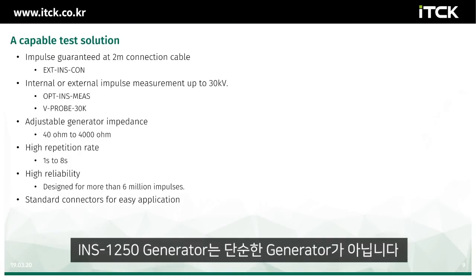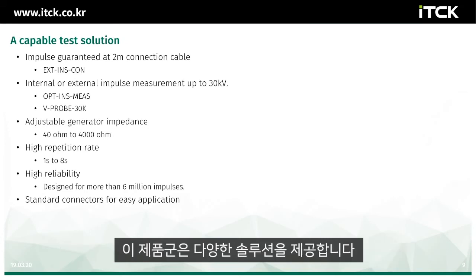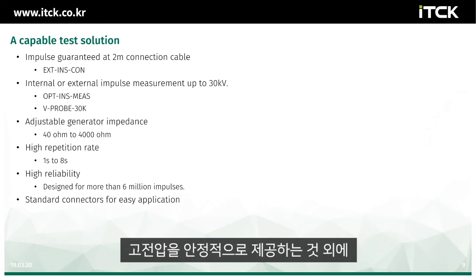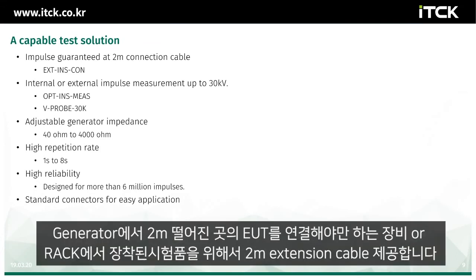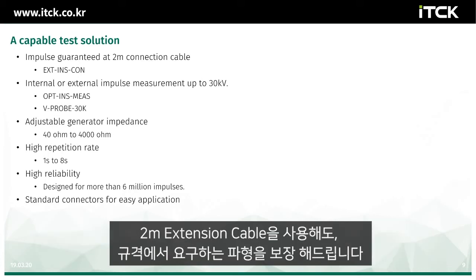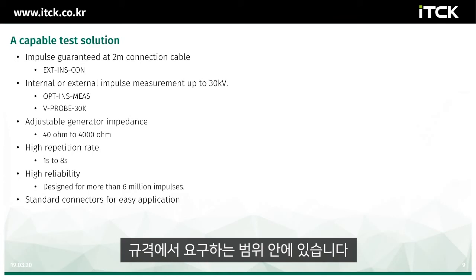INS 1250 generators are not just impulse generators. They are capable test solutions. Apart from offering the capability to deliver the impulse from the direct high voltage outputs, we also offer a 2-meter extension for testing on racks or equipment that needs to be remote from the generator. And at the end of the 2-meter extension cable, we guarantee that the impulse, wave shape and amplitudes are still within the tolerance.